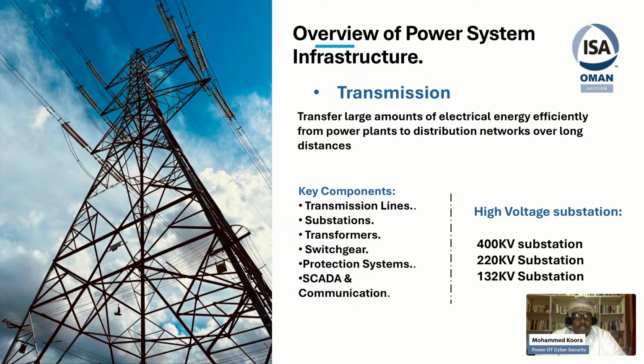What is the main component in our transmission system? Generally, you will find a network of overhead lines between the substations. In the substation, there is one main piece of equipment, which we call the transformer. Generally, transformers are of two types: step up or step down. The step-up transformer converts voltage from a lower level to a higher level, and is always located near the power plant. The other type, the step-down transformer, is located in the distribution section, near the utility, residential, or industrial area.